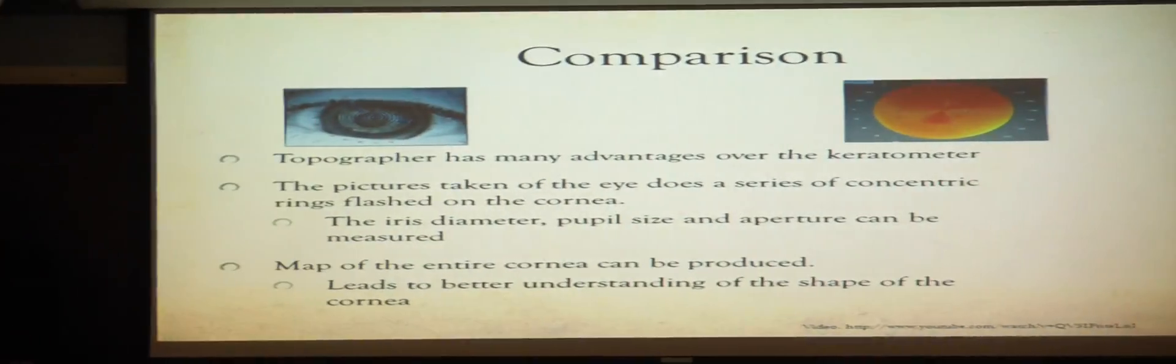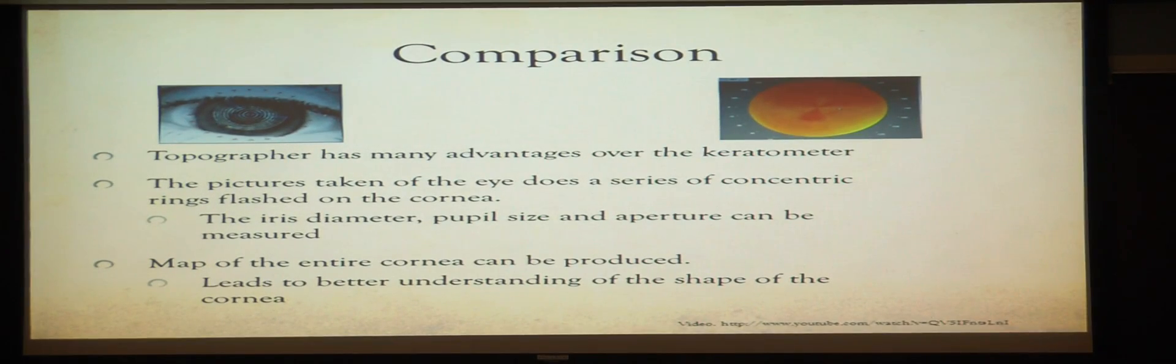Now we're going to do a comparison of the keratometer to another device, the topographer. It was found that the topographer had many more advantages over the keratometer. For the topographer, it actually takes a picture of the eye and draws a series of concentric circles, as you can see in that top picture on the left right there. From that picture, you can determine the eye's diameter, the pupil size and aperture. The right side shows the topography from an image of the eye. As you can see, it shows the entire surface of the cornea, so you can get a better understanding of astigmatism. Whereas the keratometer will only show from the center, three millimeters from the center, this little area right here, to determine astigmatism. Topography will give you a better understanding so you can apply it to contact lenses and glasses.